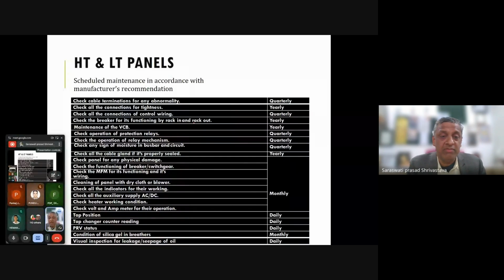VCB maintenance is done yearly, and we have to check this, since it's also connected with the transformer. Operation protection relays and mechanism should be checked, and any moisture in the bus bar circuit should be checked quarterly.